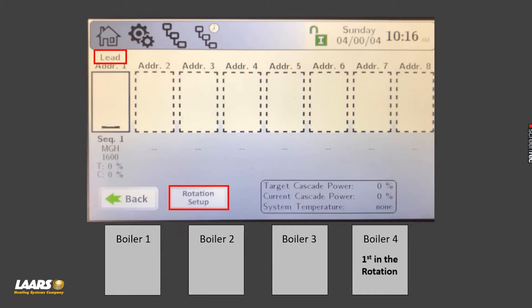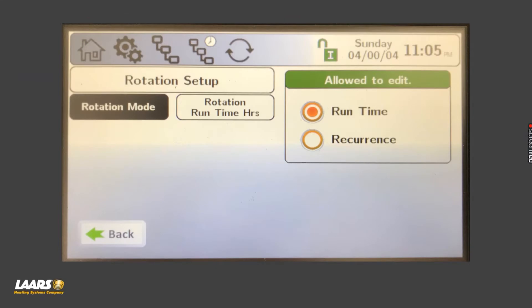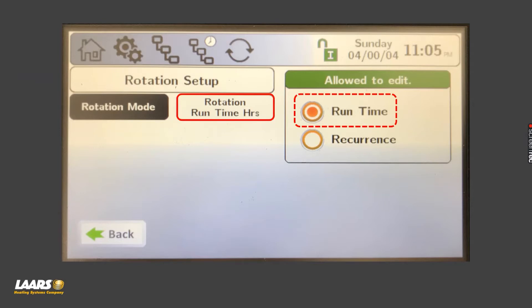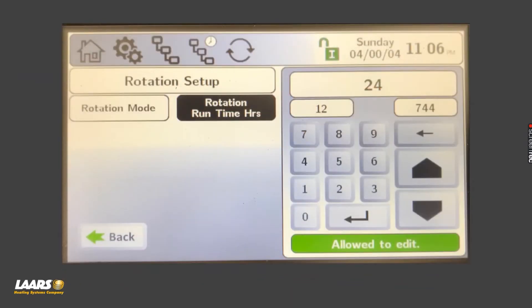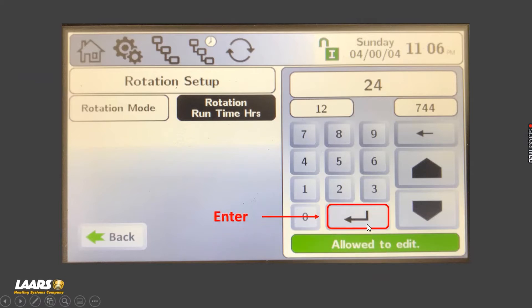Back to rotation setup — when you click on it, it gives you a couple of options. Under rotation mode, it's defaulted for run time. You click on run time hours and you can choose, for example, every 24 hours to rotate those boilers, or maybe every 48 or every 72 hours. Choose your value and click the enter button — this is the enter button on any one of the screens, even if you're at a setpoint screen choosing, say, a 160 degree setpoint.